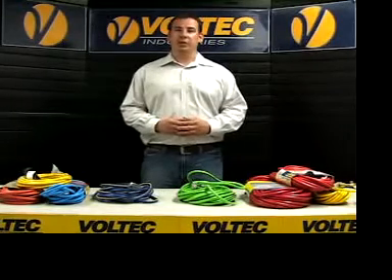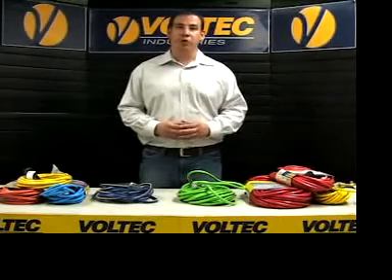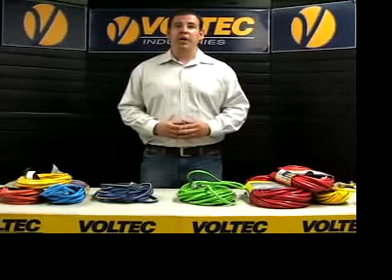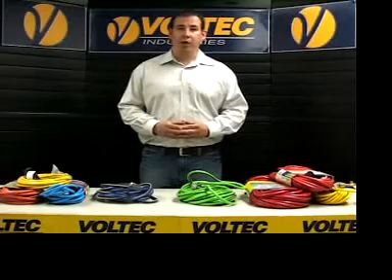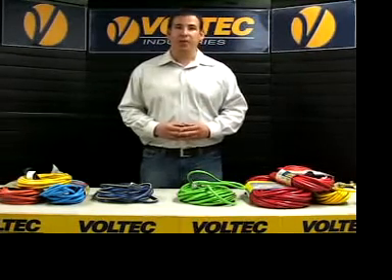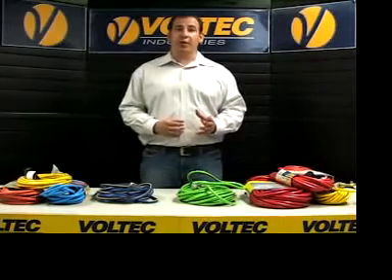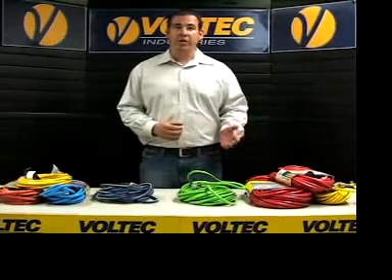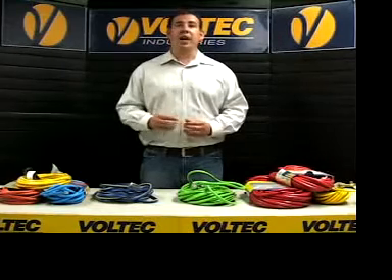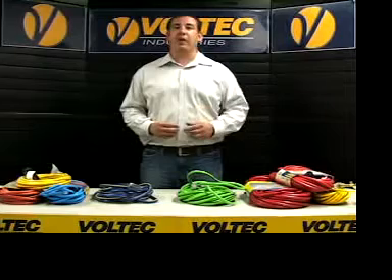When working with electrical cords, you should never remove the third prong from the plug. You should never force plugs into receptacles that don't match. Never run cords near water or other liquids. Never splice flexible cords together. Most of these safety measures mentioned are required by Cal OSHA. These are just a few tips that can be helpful in the field. Follow these guidelines and you have just created a safe and workable environment.